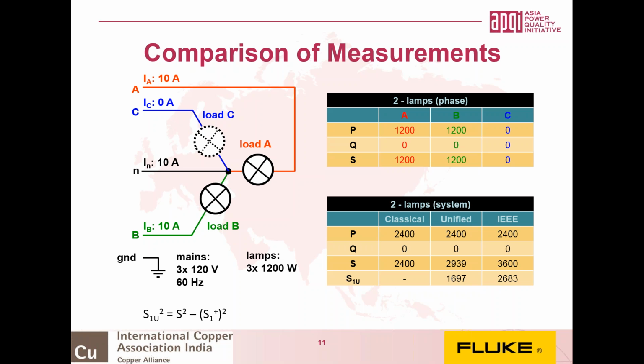So these lighting loads, when they're balanced, everything looks okay. But say we were to lose one of the loads, so say lamp 1 burns out, so that the active system power is now the only power remaining from the 2 lighting loads, or in this case 2.4 kilowatts. The apparent power from the unified method is not now 2.4 kVA, as in the classical method, but it's actually measured as 2,939 VA. So we can see that in this box here. Oh, sorry.